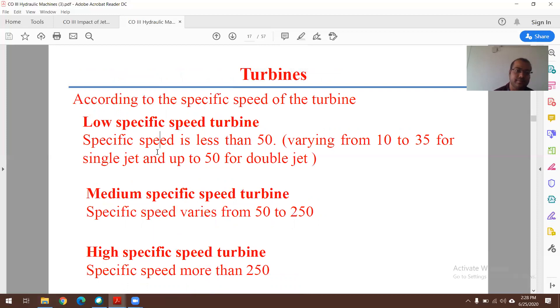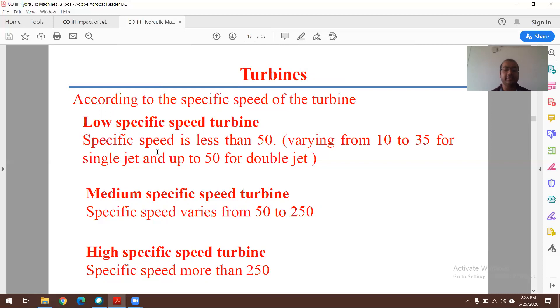Turbines can further be classified based on specific speed: low, medium, or high specific speed. Low specific speed ranges from 10 to 35 for a single jet, and up to 50 for multiple or double jets. Medium specific speed ranges from 50 to 250. High specific speed is more than 250. This concludes the classification of turbines based on specific speed.